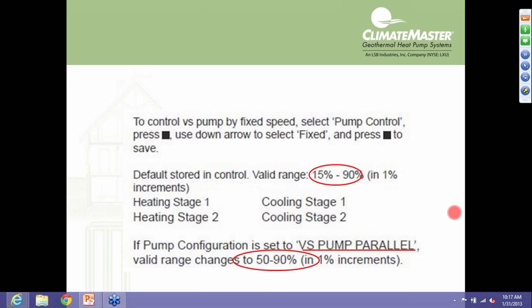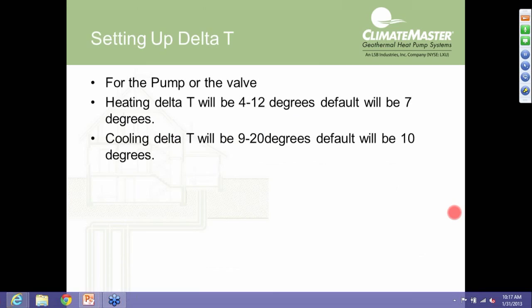Now, the range of operation here on delta T. The heating delta T is anywhere from 4 to 12 degrees. The default will be 7. With 7 degrees, under most applications, it'll achieve you in the neighborhood of 2¼ to 3 gallons per minute per ton, which is, again, our ideal flow rate, typically through a closed loop system. Now, there are some things we'll get to in a moment why you might need to make an adjustment there based on fluid type, number of circuits, those kinds of things. The cooling delta T can go anywhere from 9 to 20 degrees. Again, the default will be 10.